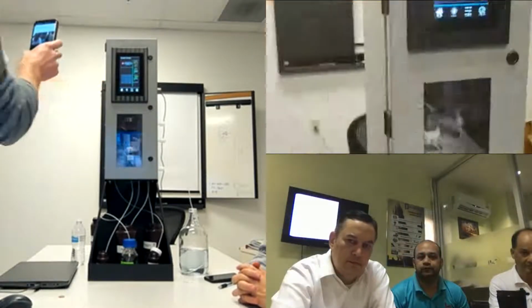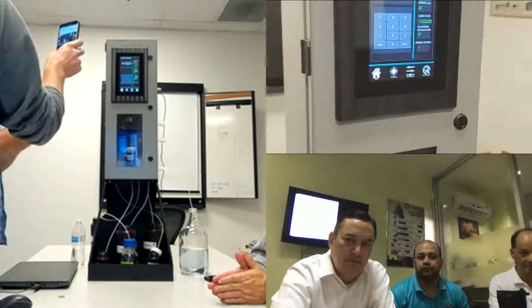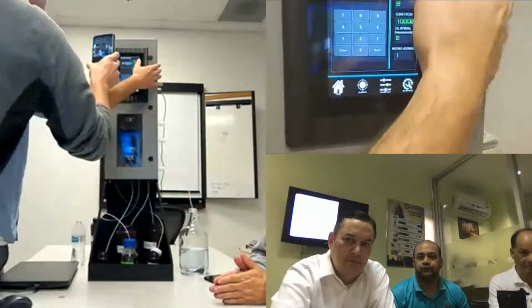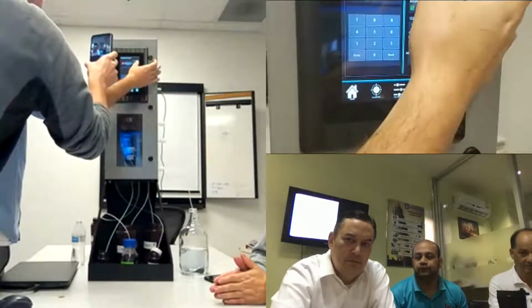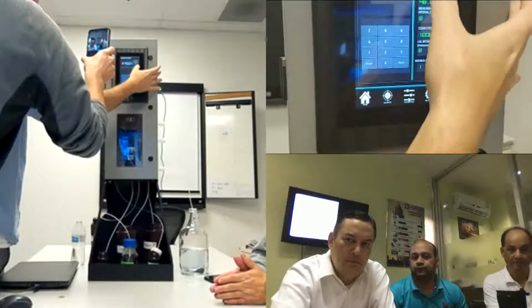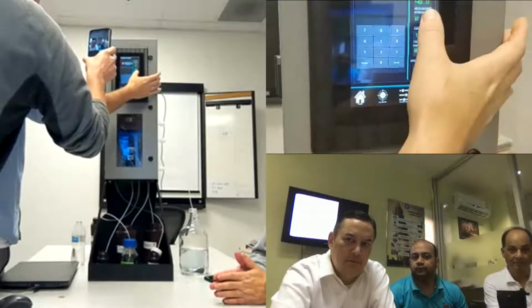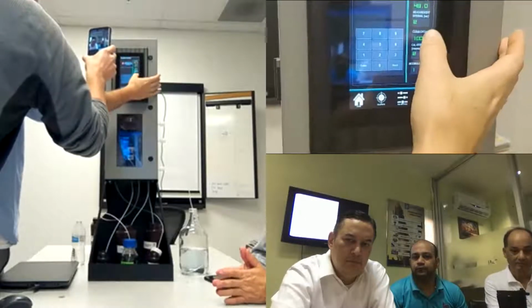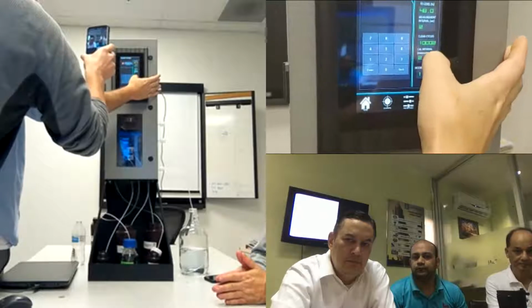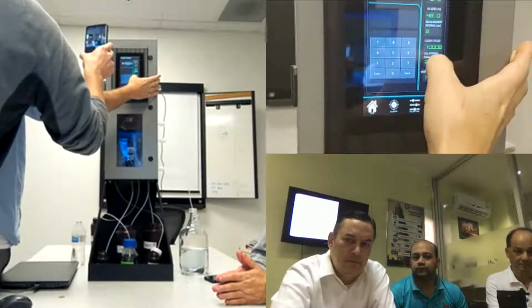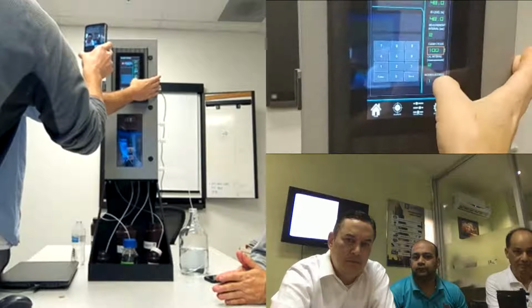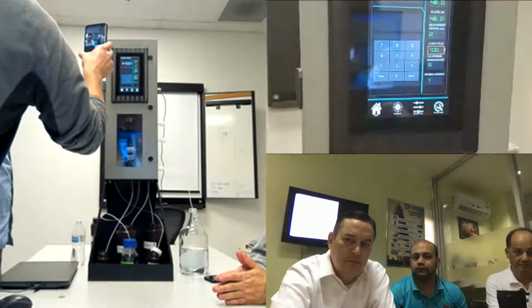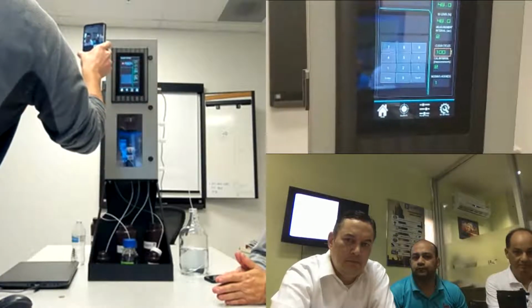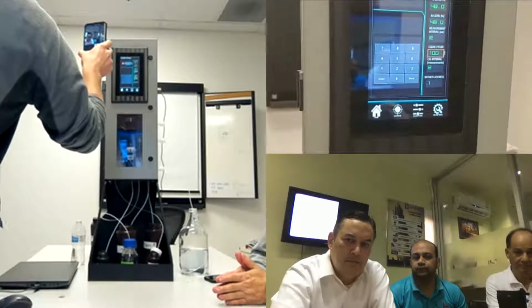So this is just the general settings screen here, where you can manipulate things. When it's time to replace your reagents, you can reset them back to 100% if you'd like. You can manipulate the measurement interval, set a cleaning cycle interval, set an automatic calibration interval, and you can actually change the Modbus address as well for Modbus RTU from this screen.